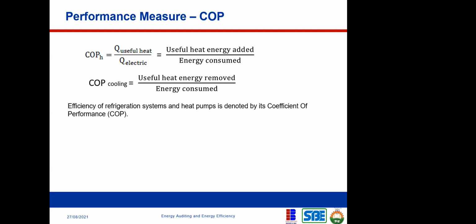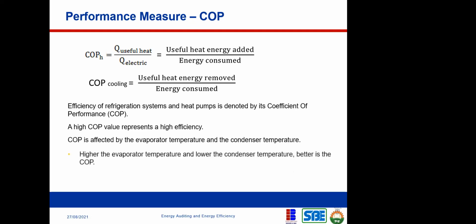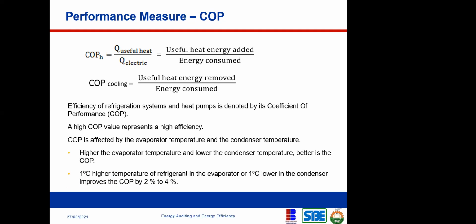It's very common when you're talking about heat pumps for an industrial process that you'll hear about COP. Even sometimes when you're talking about air conditioning systems, you might hear COP. However, air conditioning systems are more predominant with EER. I'll show you that. So a high COP value represents a high efficiency. COP is affected by the evaporator temperature and the condenser temperature. The higher the evaporator temperature and the lower the condenser temperature, the better the COP.